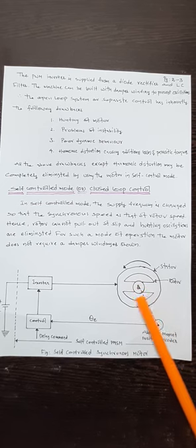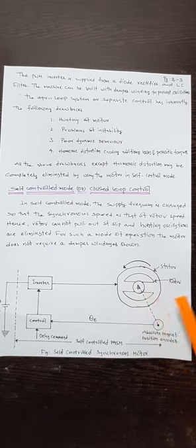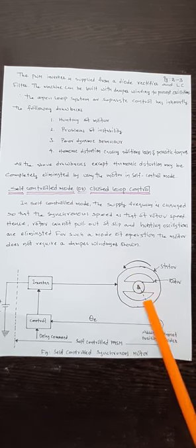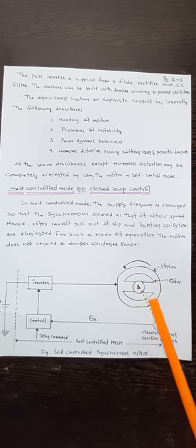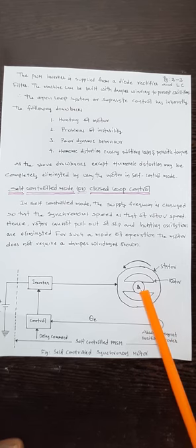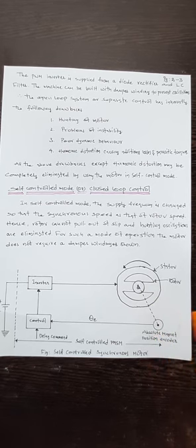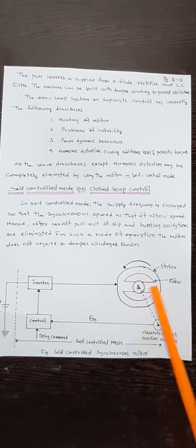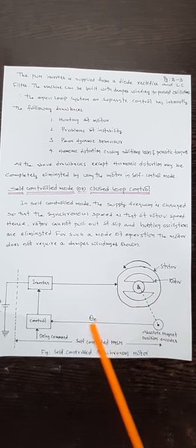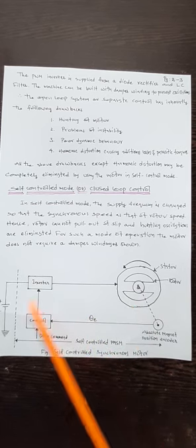That means we observe whether the rotor is able to follow the stator speed or not. Until there is a difference between stator speed and rotor speed, the absolute position encoder does not give any data. If there is a speed difference between stator and rotor, it is immediately rectified by finding the error signal. The error signal is processed through a control to the inverter.